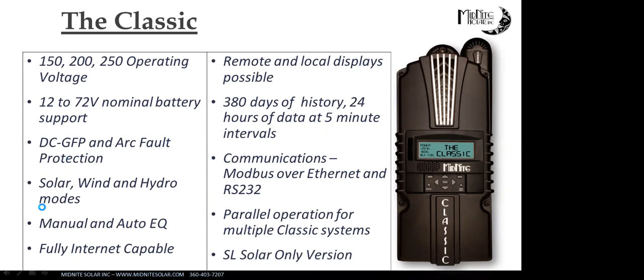So again, follow the max voltage the manufacturer calls out. Make sure you're using gear that's DC rated. AC is definitely not the same. I've seen a lot of people using Square D breakers, and I know they carry a little bit of a DC rating, but usually your overcurrent protection in DC is not a place to cheap out. Is your overcurrent protection load break rated? That's another one that's important. When you're looking at El Cheapo DC breakers on Alibaba or something to try to save a few bucks, are they actually load break rated? Are they listed? Look for those things.